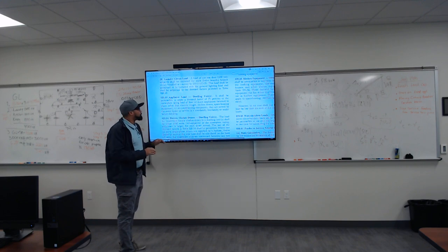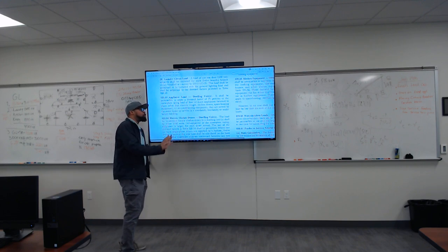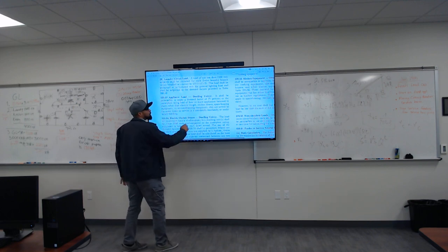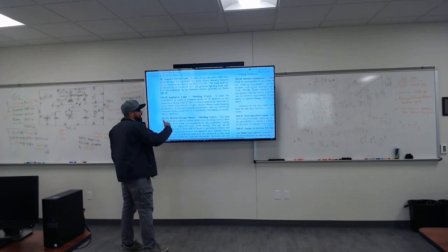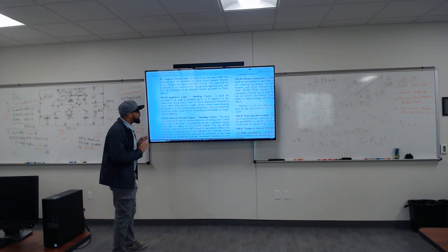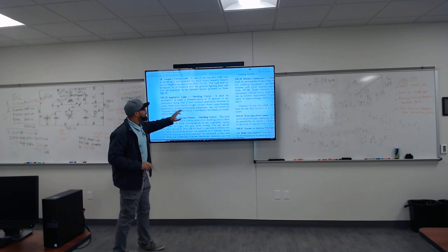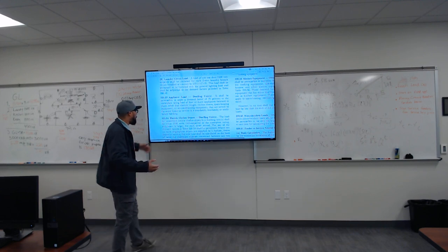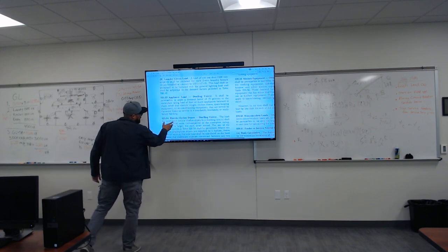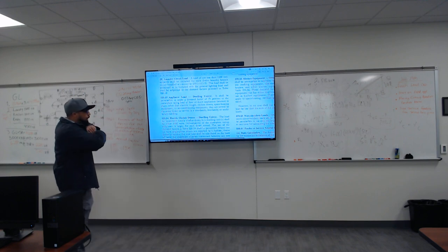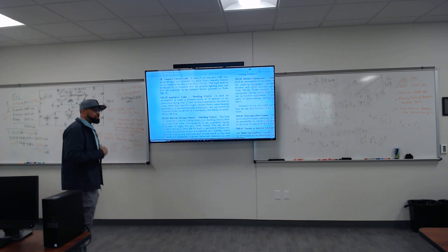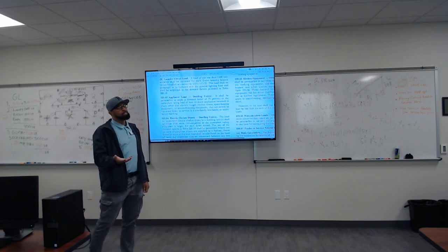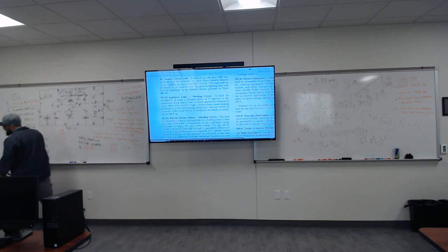Not a clothes dryer, because the NEC has articles dedicated to the clothes dryer, which we're going to get to in a few moments. The space heating equipment, we're going to get to that. Air conditioning, we're going to get to those things. But for fixed appliances, for four or more, you have to use 75% in all residential dwellings, which is a house. See, look, electric dryers is one article below. We're not going to talk about that until we actually get to it. All right, so you're probably wondering, for this practice home that we're doing the calculation for, what appliances do we have? Let me bring that up.